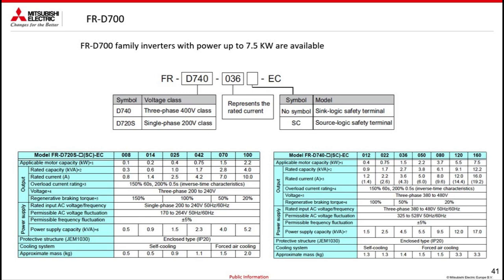Below we see the tables where we can see what the available FRD sizes are, obviously also based on the power supply network. As regards the FRD 720S model, therefore 230 volts single phase, we start from a minimum of 0.8 amperes, which corresponds to 100 watts, up to a maximum of 10 amperes, which corresponds to 2.2 kilowatts. As regards instead the 400 volt three-phase, we have 1.2 amperes, which corresponds to 400 watts, up to a maximum of 16 amperes, which corresponds to 7.5 kilowatts.